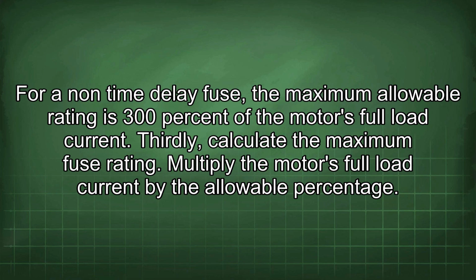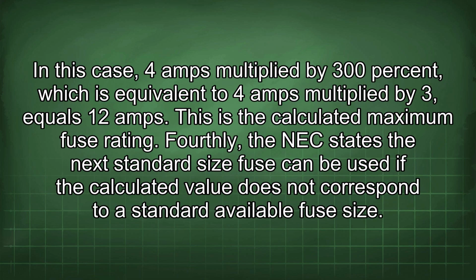Thirdly, calculate the maximum fuse rating. Multiply the motor's full load current by the allowable percentage. In this case, 4 amps multiplied by 300%, which is equivalent to 4 amps multiplied by 3, equals 12 amps. This is the calculated maximum fuse rating.